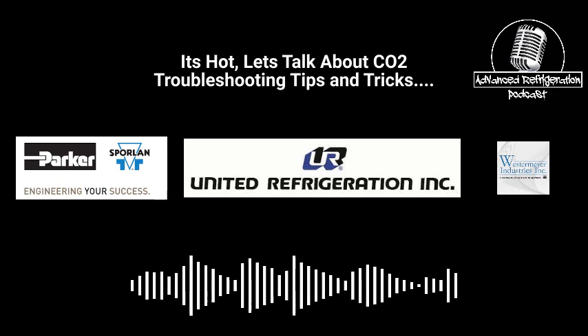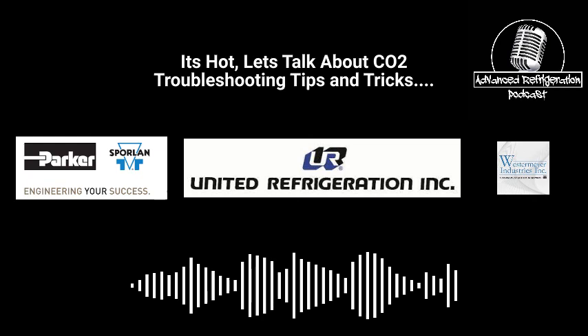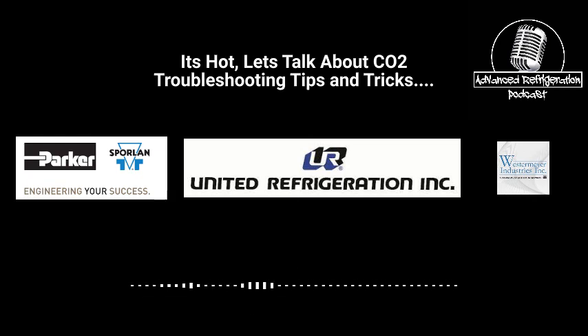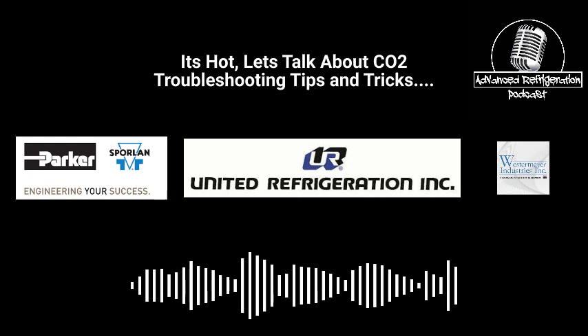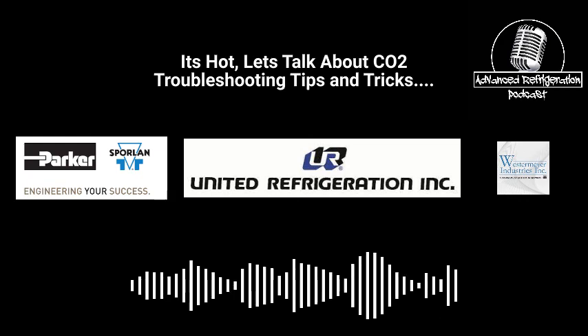How many times do you find where the strainer and those ICM valves are plugged up? The high pressure valves, on occasion. If it's one manufacturer from Canada, it's like every time; we usually clean them on startup, but they're filthy. Most of the US stuff, not very often. Usually, if you have a plugged strainer, you'll have high pressure, high subcooling, and high valve percentages on the high pressure valve. It's going to want to stay open, like 100 or whatever the max is, trying to open up, and it's still going to be flashing off there at the valve, right?